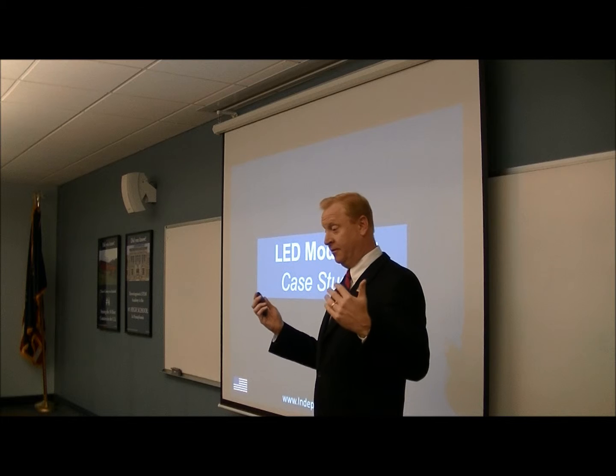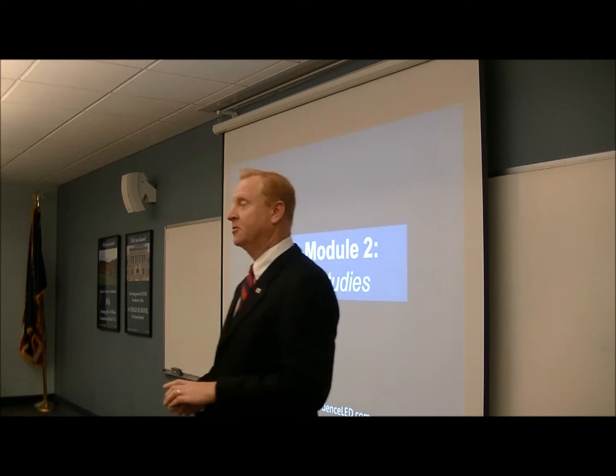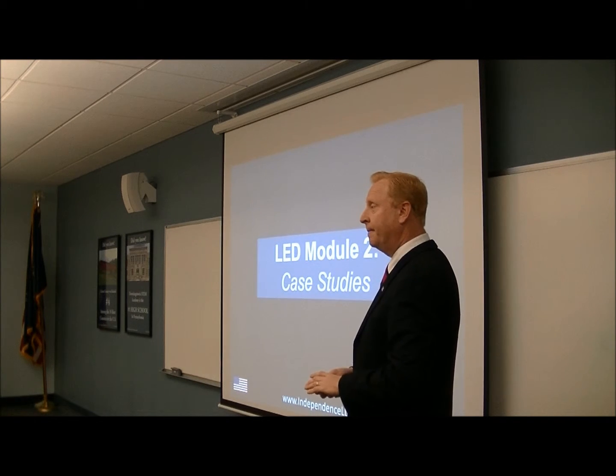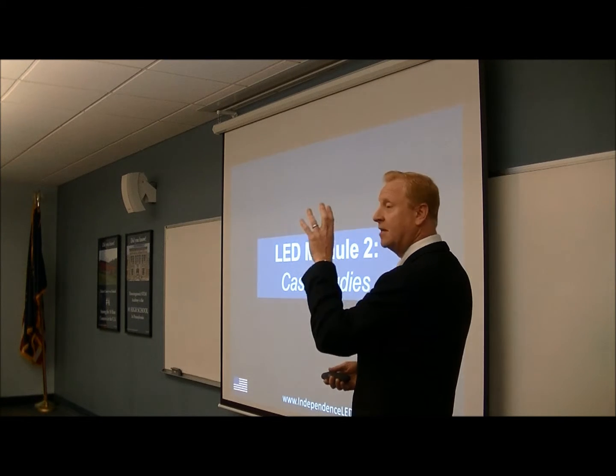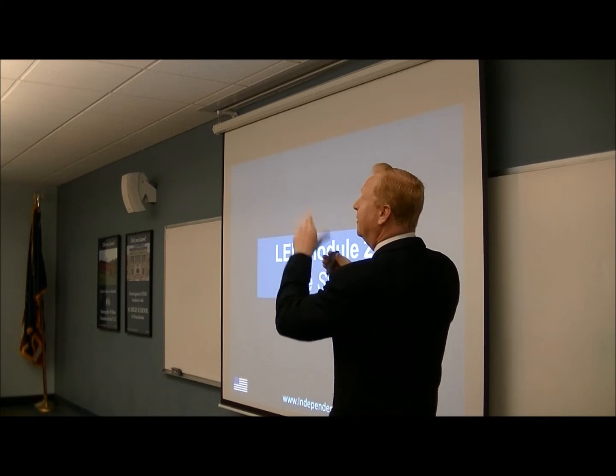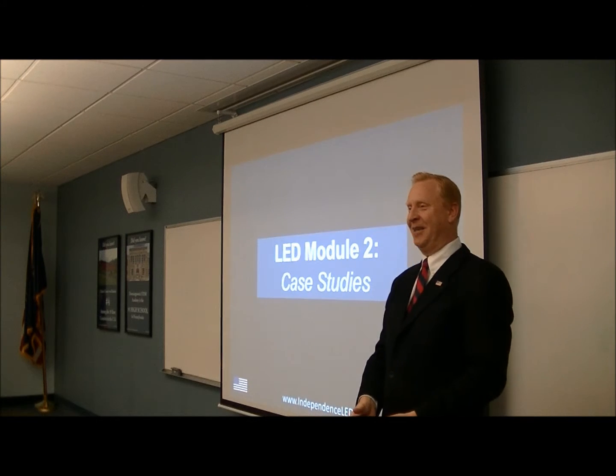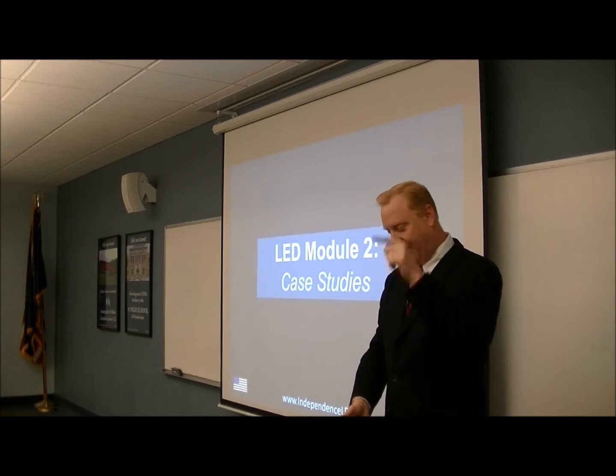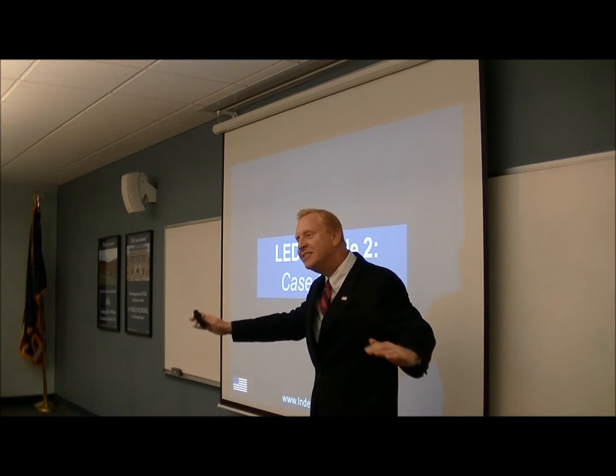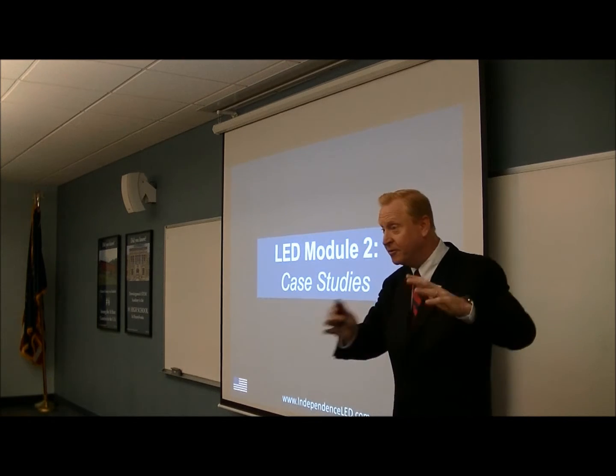Good news is, and I'll tell you this as a manufacturer, the layers of phosphor that we put on the diodes dictate the Kelvin. So when you are on the buy side, ask for samples to see. What I tell people is don't get just one sample, get a pair of them so you can look at them next to each other. So it might be the 3500, 4000, 5000 series in pairs, and run your foot candle meter, or your provider, directly underneath each fixture, but then between the two. So you can actually see the beam angle. Remember the diagram that had the wide versus the medium versus the narrow?